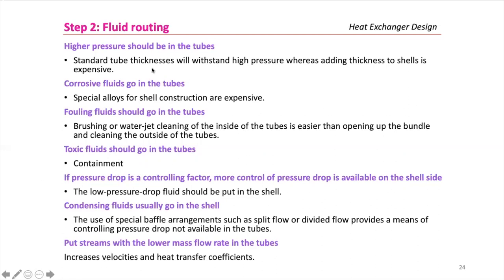General guidelines for fluid routing: higher pressure fluid should be in the tubes; corrosive fluids go in the tubes (leaks contained in shell); fouling fluids go in the tubes (easier to clean by brushing or water jetting); toxic fluids should be in the tubes for containment; if pressure drop is controlling, put the low-pressure-drop fluid in the shell; condensing fluids usually go in the shell; put the stream with the lower mass flow rate in the tubes to increase velocity and heat transfer coefficient.